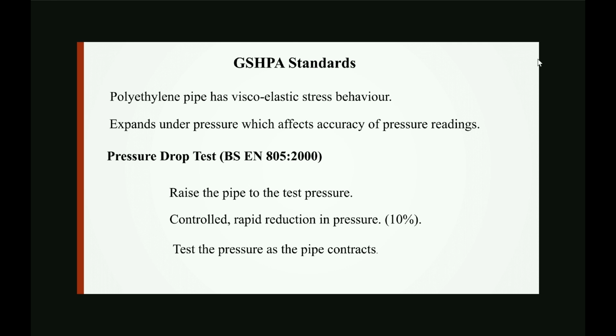The pressure drop test in BS-EN 805, and by the way, that's another one of the standards which is mentioned in our statutory instrument as one to work to avoid the permit. First of all, you raise the pressure to the test pressure, then you have a controlled rapid reduction in pressure of 10%, and then you test the pressure of the pipe as the pipe actually contracts.